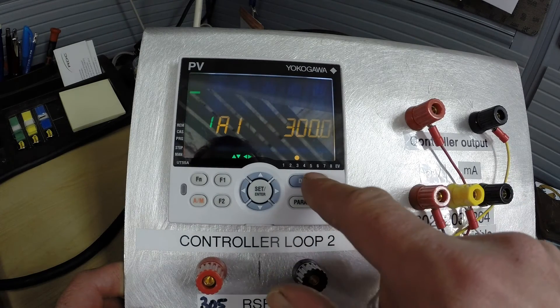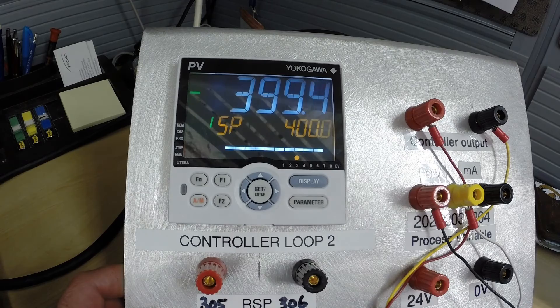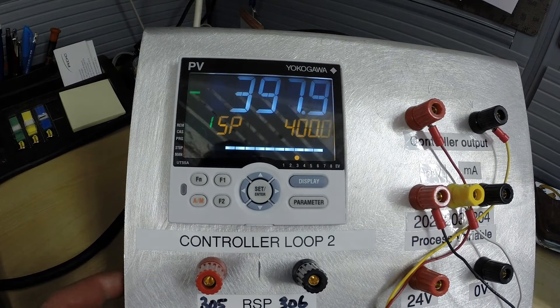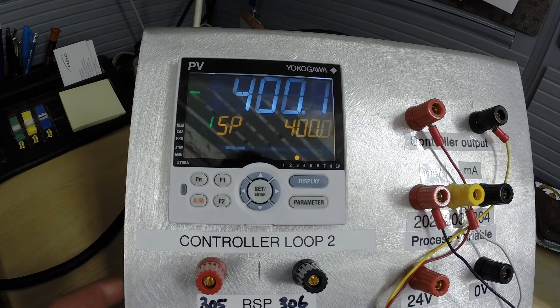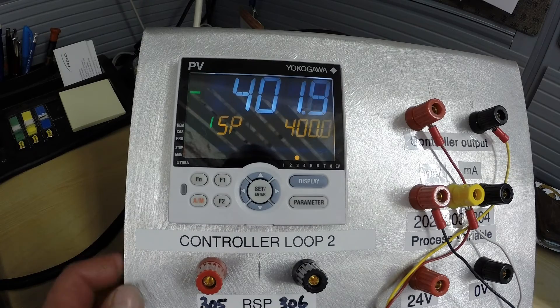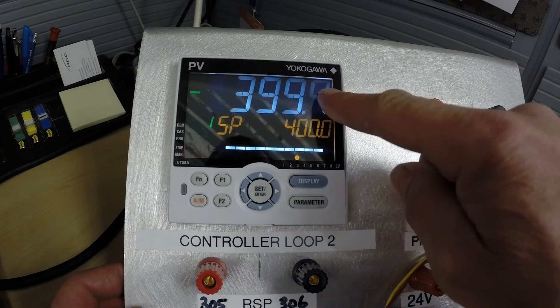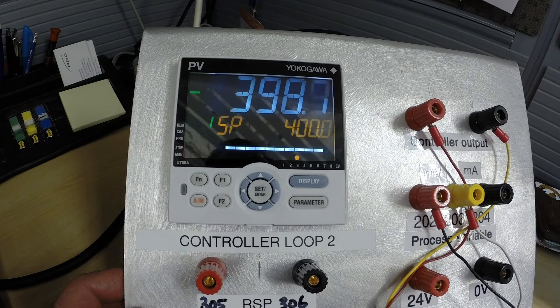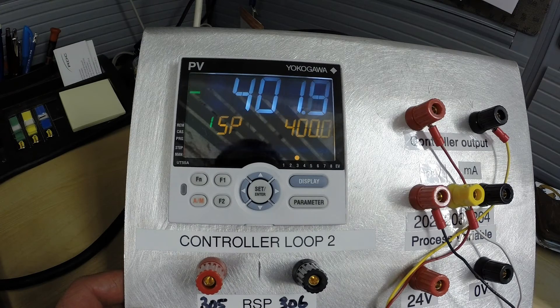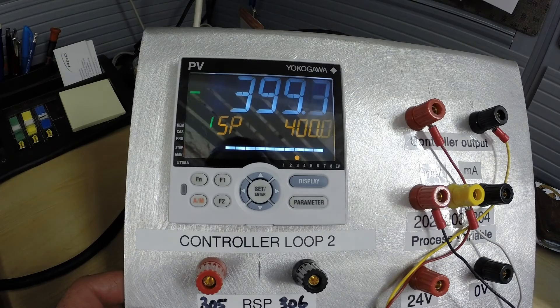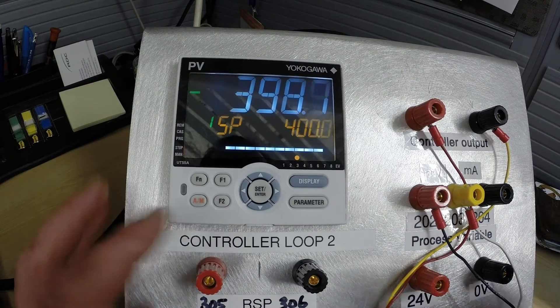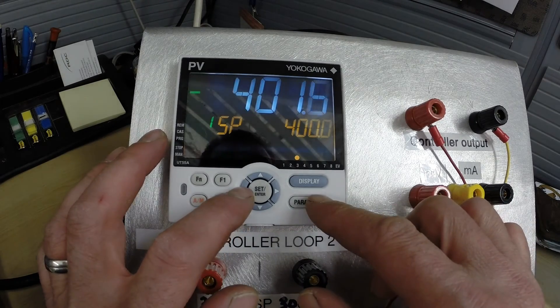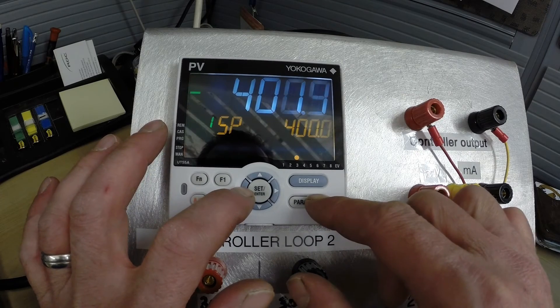And we will press display to back out of that. So now we have the controller set up so that we will alarm at 300 degrees Celsius but we also want to set it up so that this display will change color to give a visual indication that we are actually in alarm beyond just having the alarm output relay kick in.